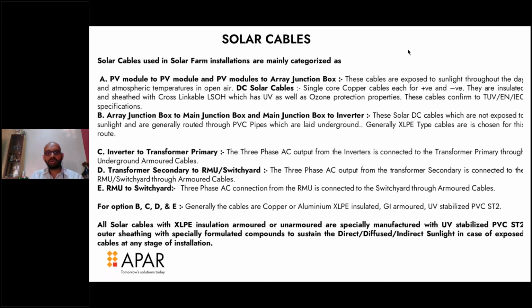The next is the array junction box to main junction box, and the main junction box to the inverter. Now these cables are generally not exposed to sunlight, and are routed through PVC pipes. So here XLPE cables are used for this category. Then you have the inverter to the transformer primary, which is a 3-phase output. From the inverters, it is connected to the primary. These are generally underground armored cables, which you can call normal AC cables. Then you have the transformer secondary to the RMU switchyard. These are the cables from the secondary to the RMU, and are armored. These are generally for 11 kV and above. And then you have the 3-phase connection of RMU to the switchyard, with armored cables. These are right from, say, 1.8, 3.6, 11, 22 kV, depending on the use.